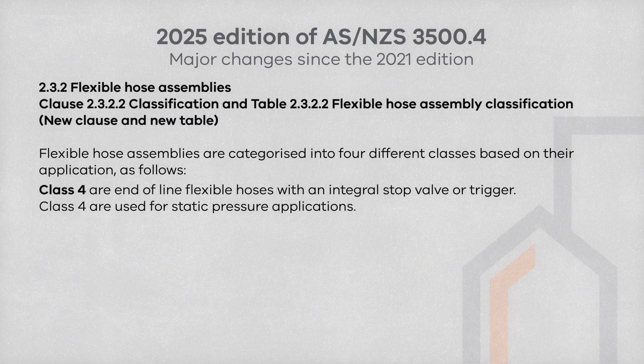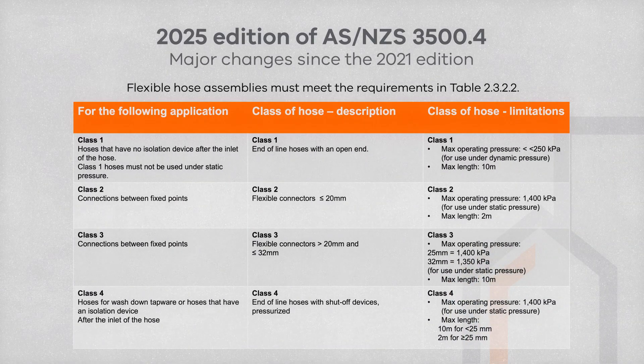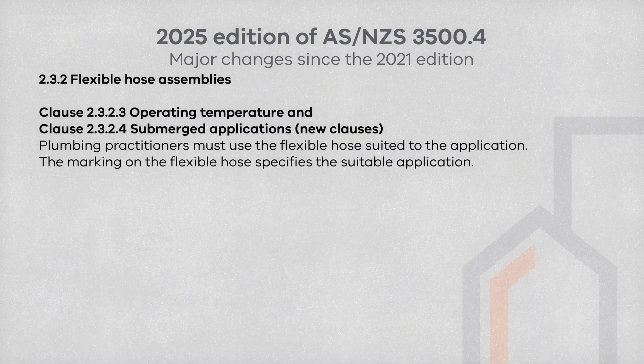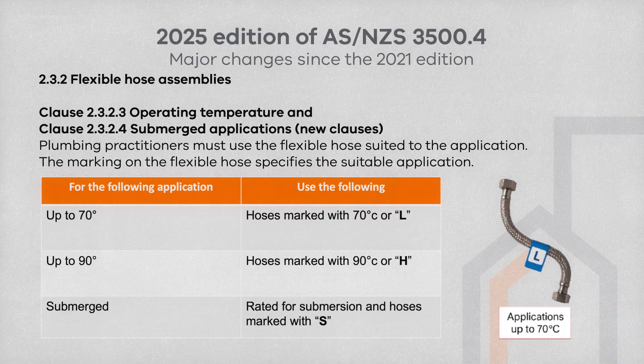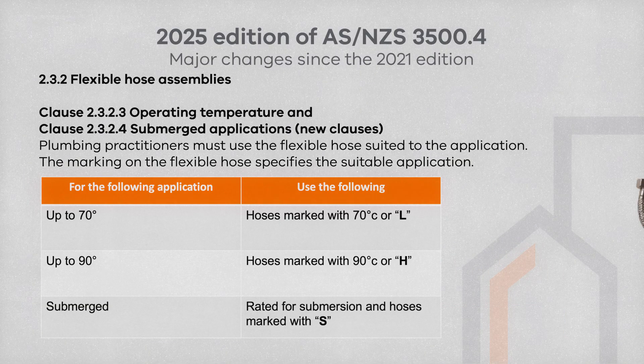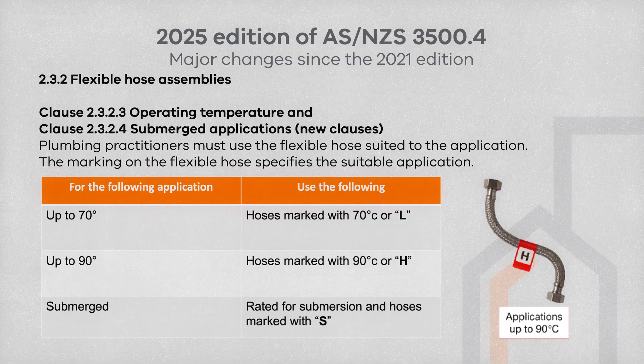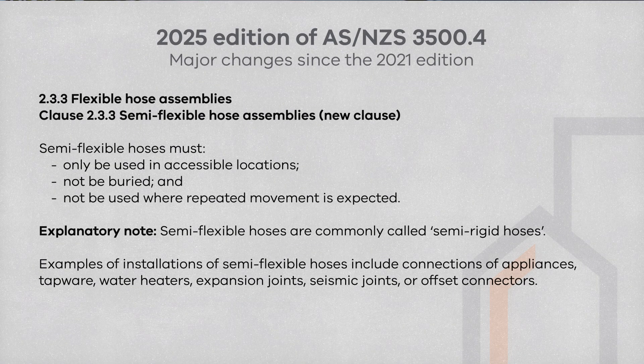Ensure the appropriate class of hose is used for the correct application. Classification Table 2.3.2.2 is again provided here, showing the requirements of flexible hose assemblies dependent on class, application and limitations. Just as in Part 1, there is a new Clause 2.3.2.3 regarding the operational temperature range of flexible hose assemblies, also covering submerged applications. Hoses must be marked with the appropriate temperature rating or the corresponding letter to suit the application. Semi-flexible hoses, commonly called semi-rigid hoses, are also covered in this section, and must meet the applicable requirements where selected for use.